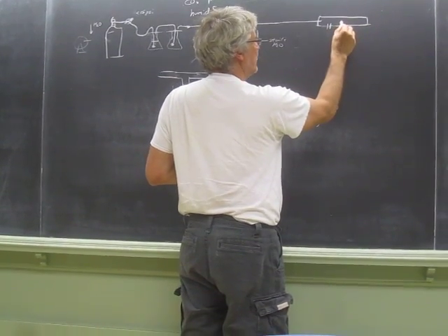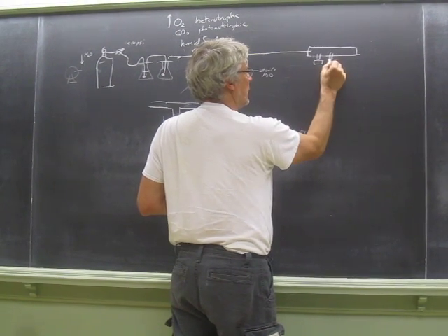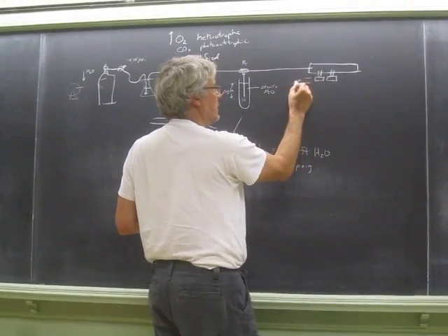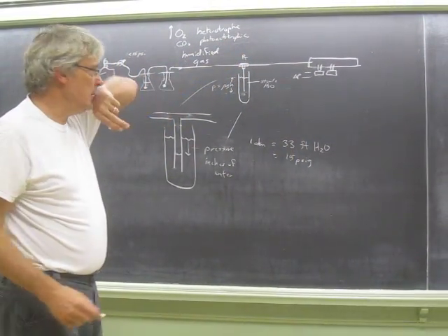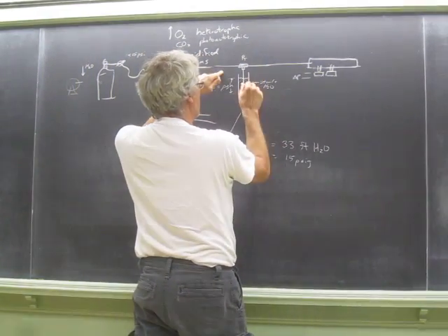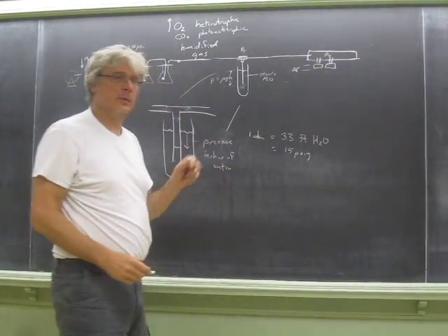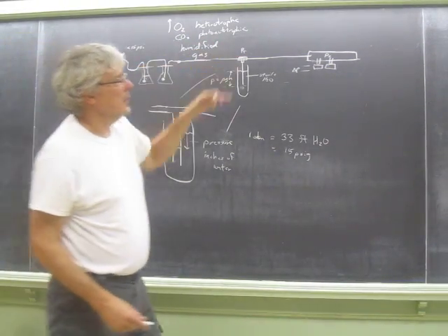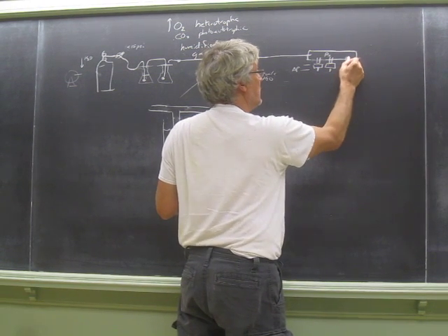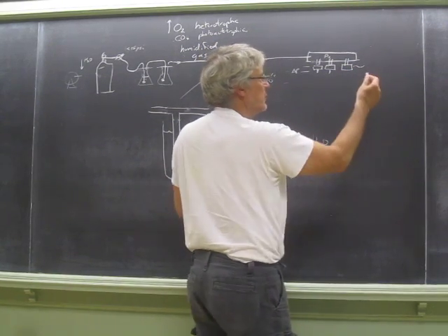And the idea then is that for the flow rate going through these filters, there's going to be another pressure drop across here, and that pressure drop is going to be relatively large relative to the pressure here. So the pressure here and everywhere in this is going to be the same as the pressure at the T itself. And then the pressure drop across there is going to be the same for each additional filter that I place on there. And this is a typical filter.